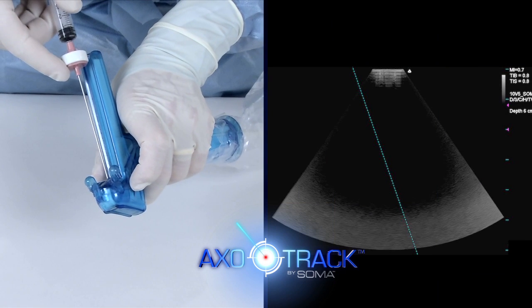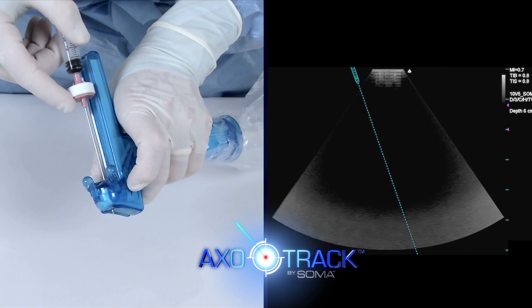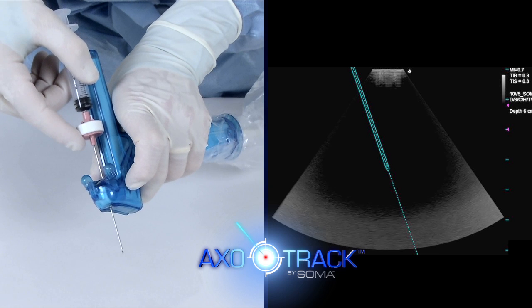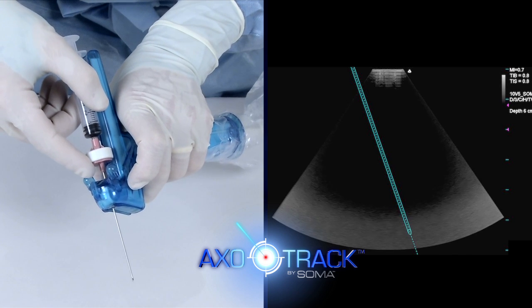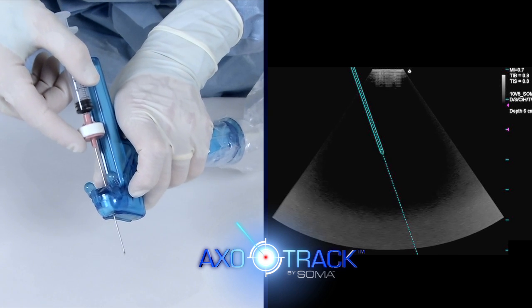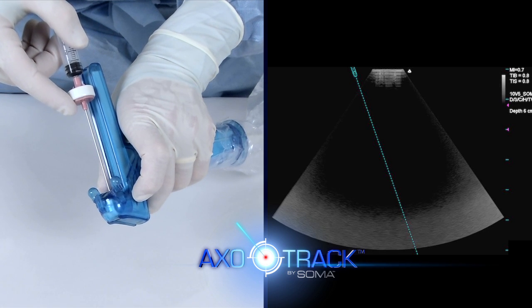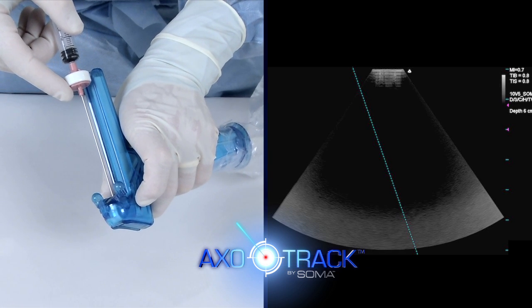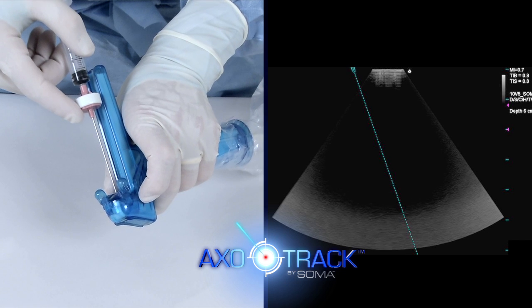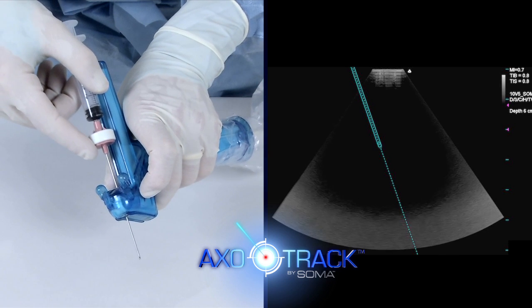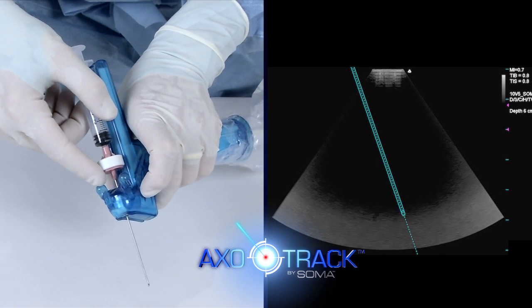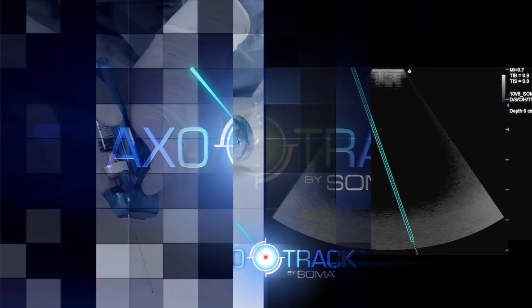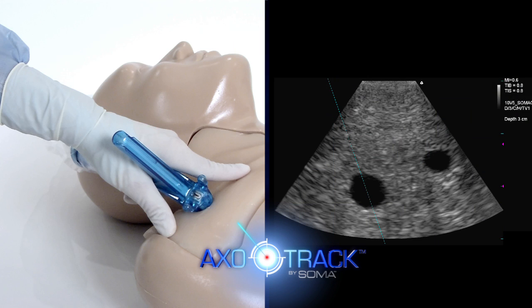As the needle is passed through the needle guide, the sensors in the probe precisely monitor the position of the magnet on the needle. The system automatically combines the magnet location information from the magnetic sensors with the ultrasound images acquired from the beamformer to produce a virtual image of the needle on the sonogram in real time. You can see that the virtual needle mirrors the motion of the actual needle. The AxoTrack system consists of AxoTrack virtual needle technology within an ultrasound probe and an AxoTrack sterile procedure kit.